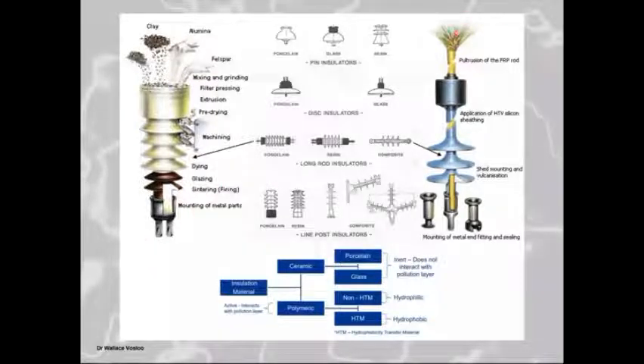Now, going to a composite insulator, there we start off with a fiber reinforced rod. So we take these fine single thread glass threads which come on a roll, and there are hundreds of these rolls placed onto a rack. All these little fibers are taken through a grit which shapes them into a certain pattern, and then they pull through a resin and hardener bath, and then they pull through a pultruder, and they are formed into a rod. As it pulls through, it starts to cure, and the rod then becomes this long fiber reinforced rod.